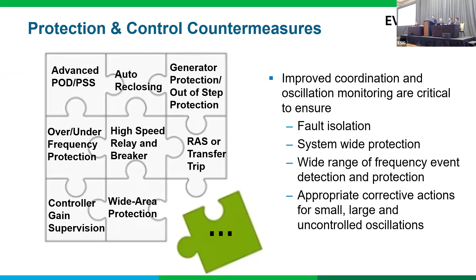So what's the difference when you have offshore wind? The difference is when you have a larger scale of wind, you will have a much larger range of frequency events, which could not be fully covered by existing relays. There are events observed around the world that have proved they still have gaps. So you still need to continuously study it and improve the relays. You may need more system-wide protection depending on the study result.